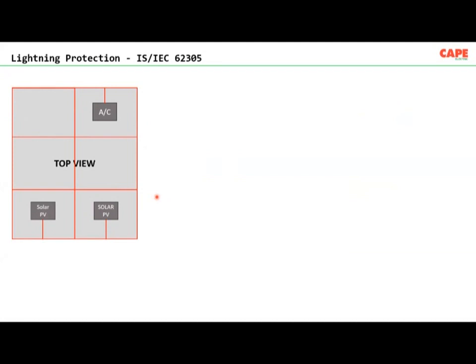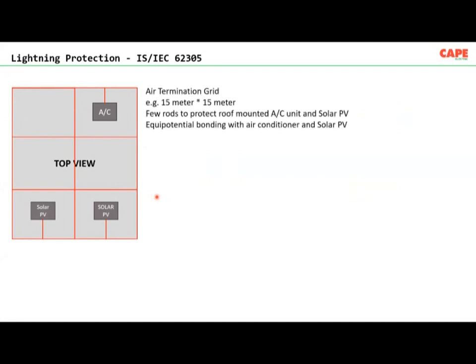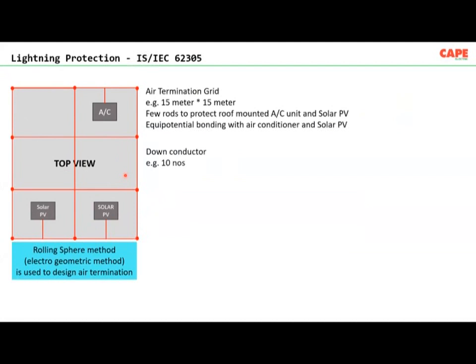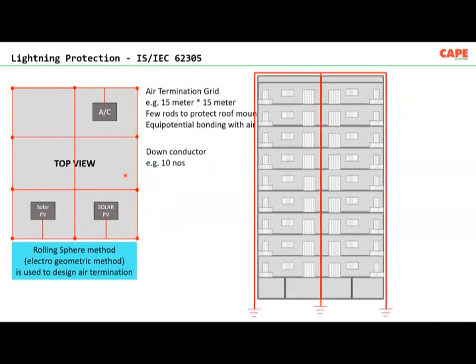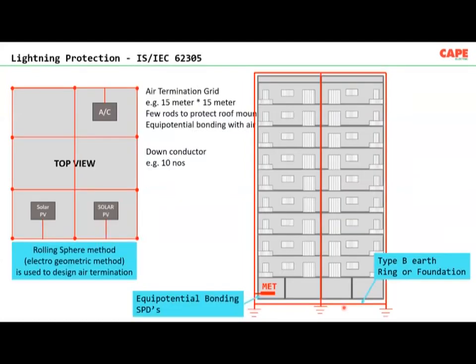You know very well that for lightning protection, the Indian standard, 62305, advocates a mesh at the top of the building, then several down conductors, for example 10 down conductors in a typical building. Then equipotential bonding, that means the down conductors and the MET are connected together. Then you can have earth electrodes in soil or earth electrodes inside your concrete and so on. This is the explanation from a global, very well accepted standard, 62305.